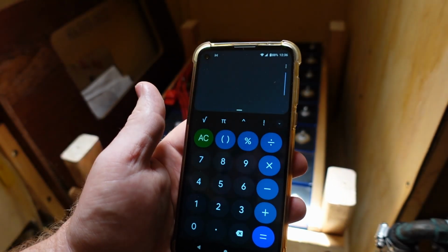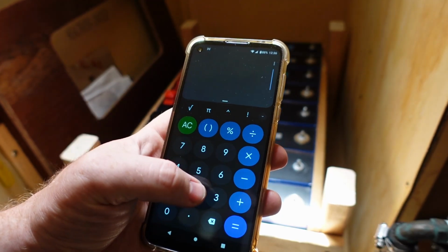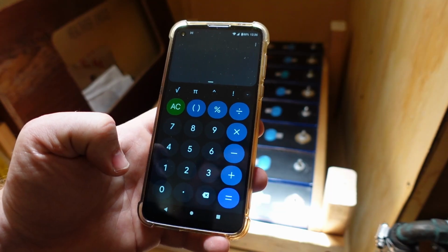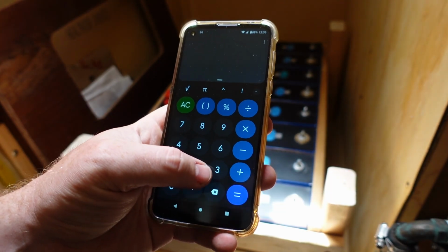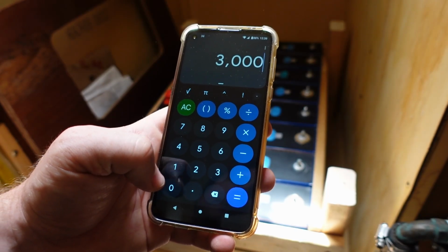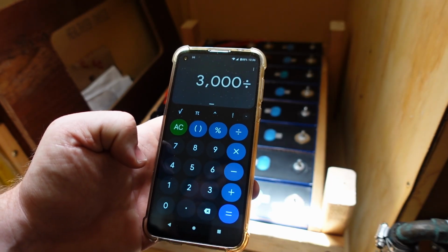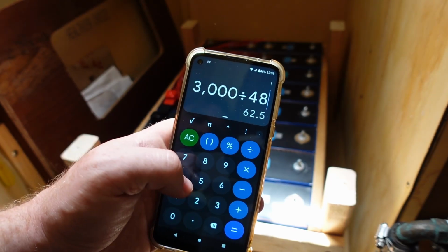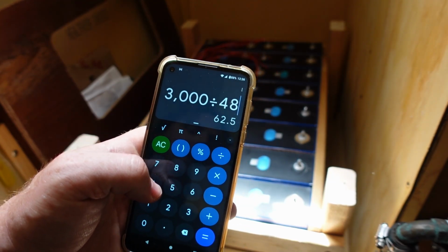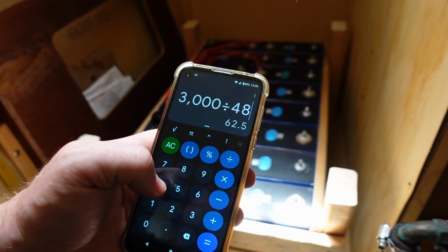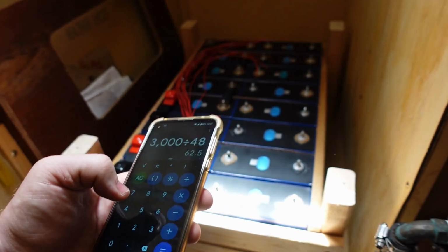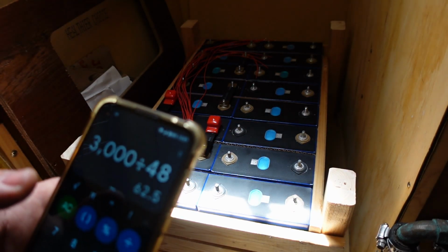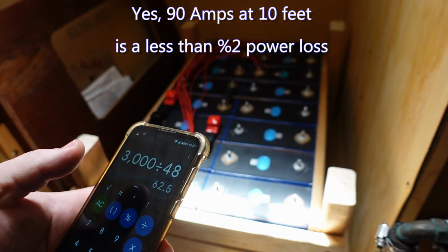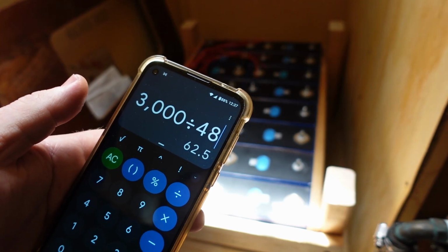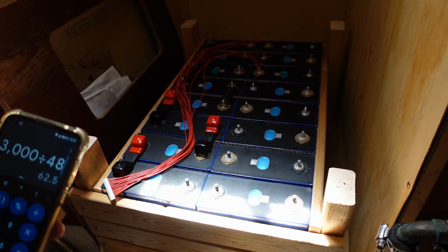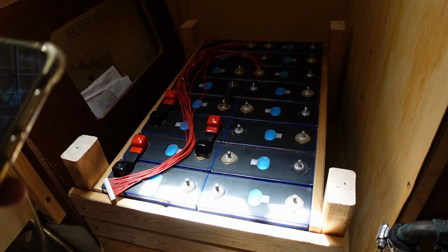Alright, a little bit of math: we have 3000 VA, but we'll essentially call it 3000 watts - depending on load that could be true or not, but it's close enough for this estimate. So we take 3000 and divide by the pack voltage, which is 48, giving us 62.5 - that's the maximum amps the Victron should be able to pull. I know it can pull more for short periods, but a 6 gauge wire of this nature is rated to about 90 amps, though I might correct myself on that. So that's fine, and I'm going to put a 63 amp breaker on the line going to the inverter. We should be good for using this for the house loads of the boat.